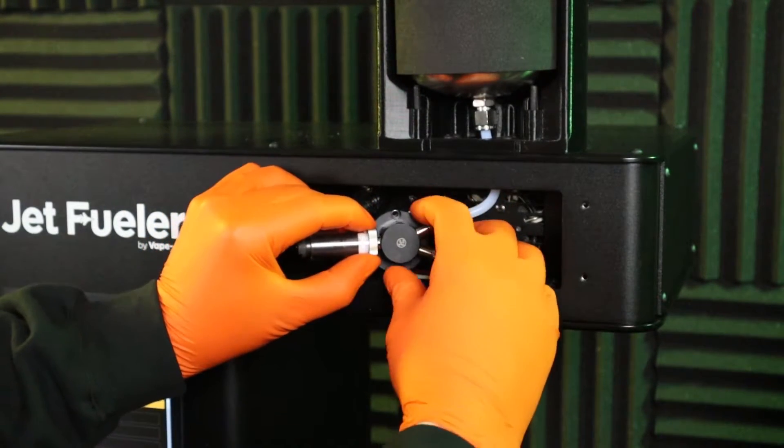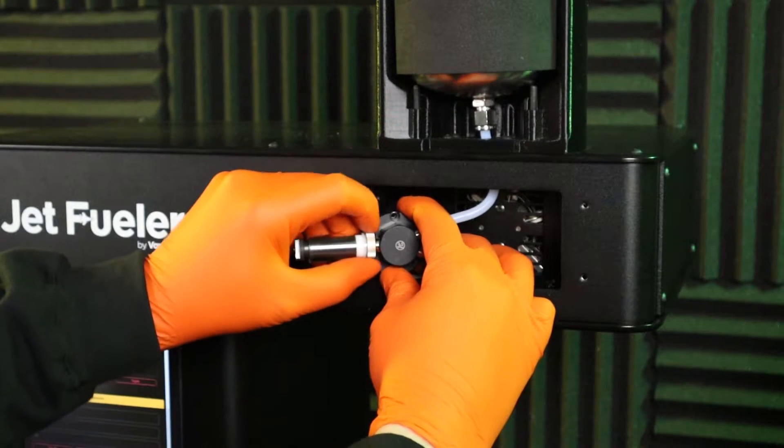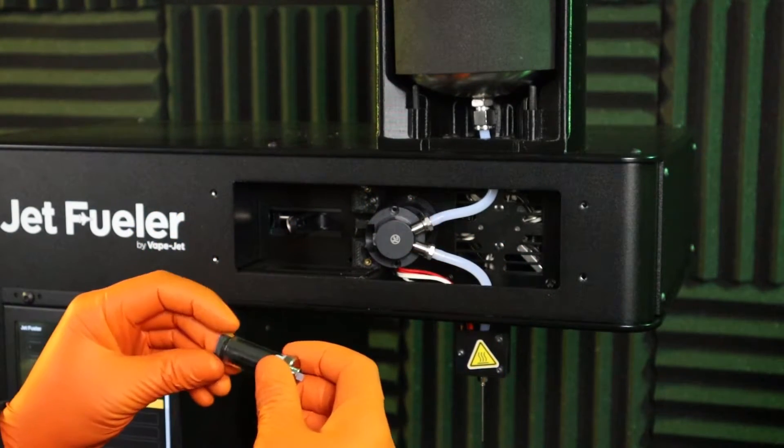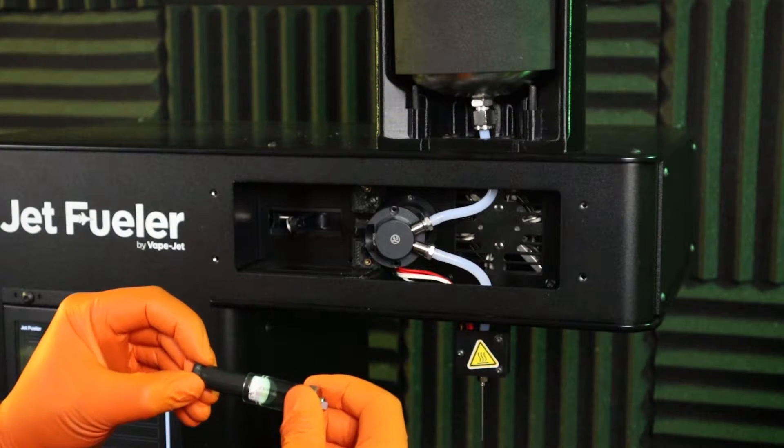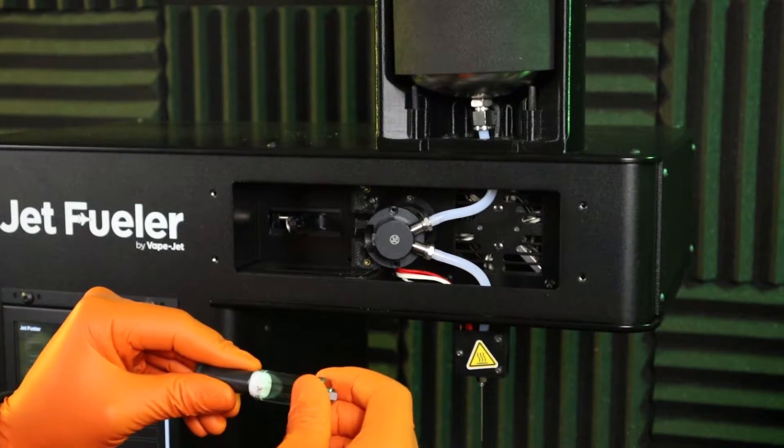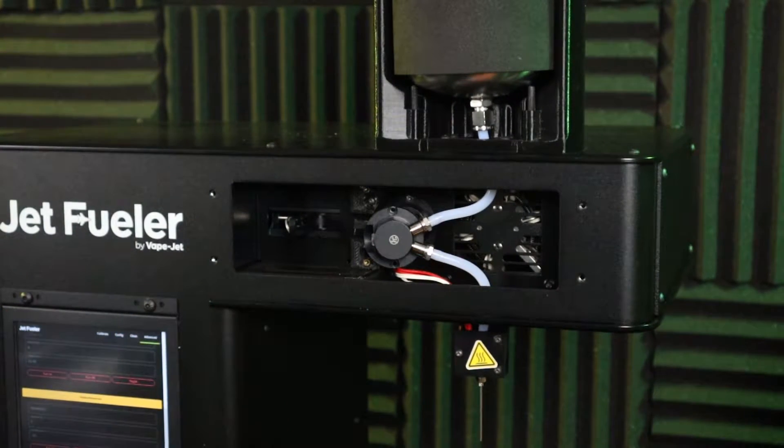Disconnect the syringe from the valve body by rotating counterclockwise when viewed from the plunger end of the syringe. Carefully pull the plunger out of the syringe body and place both pieces into a beaker of 99% isopropyl alcohol.